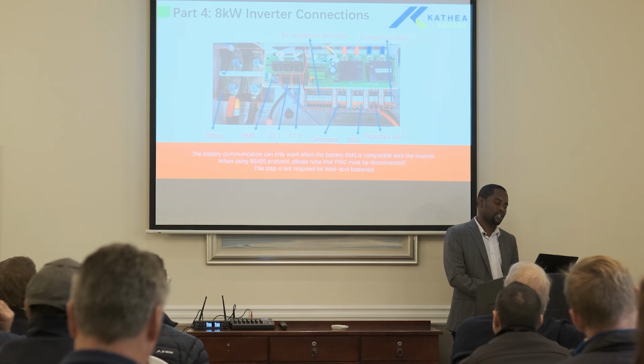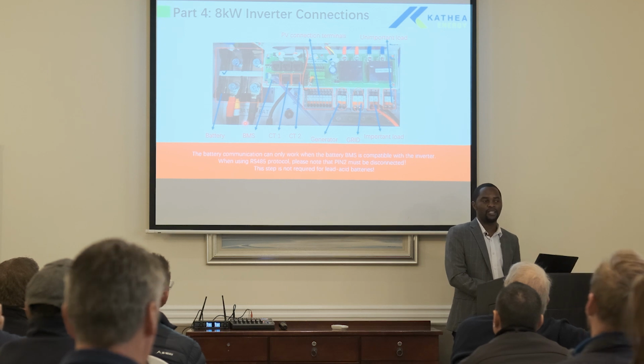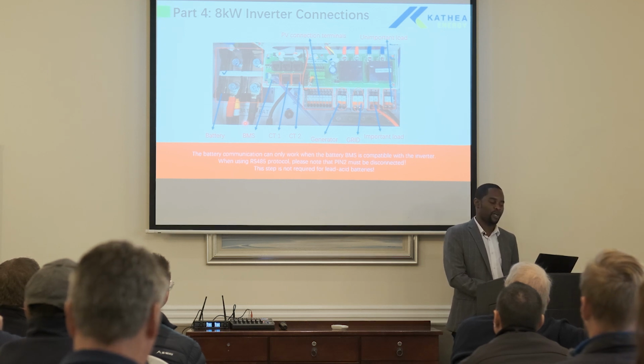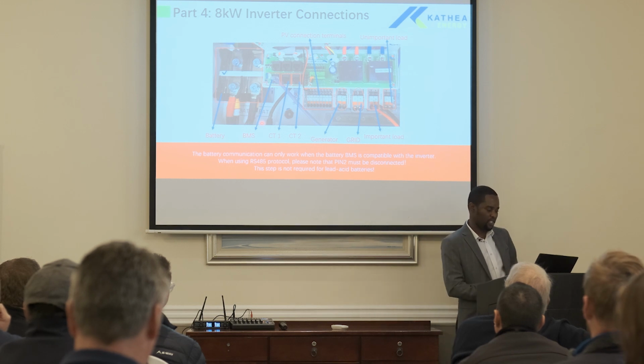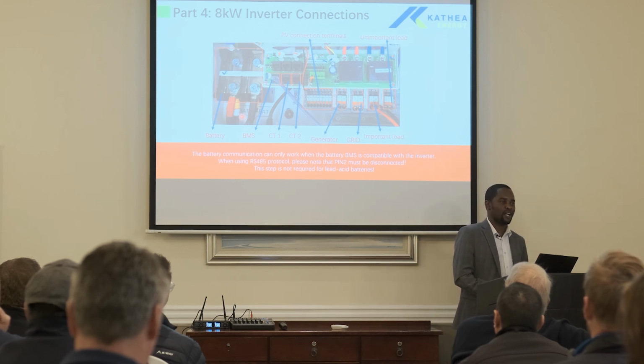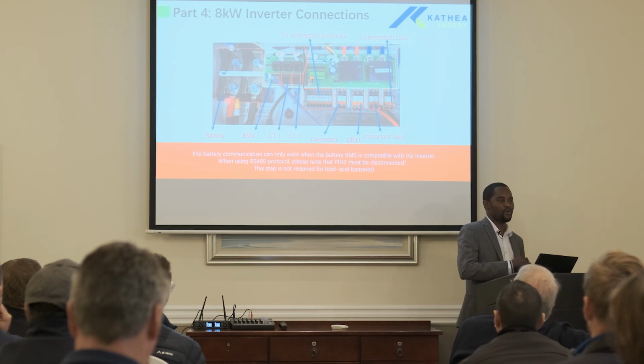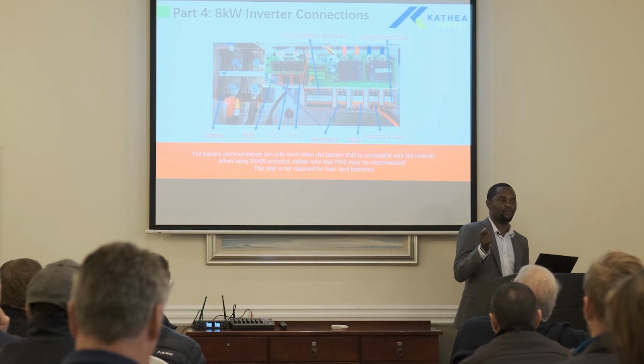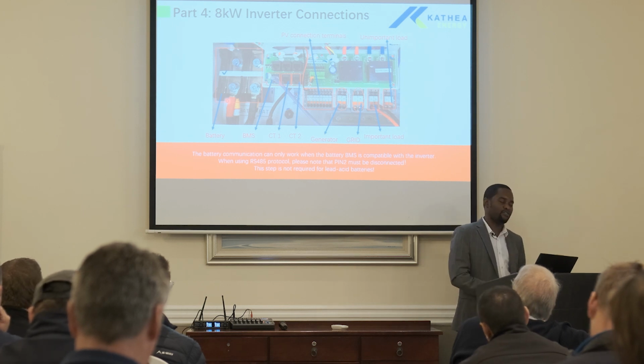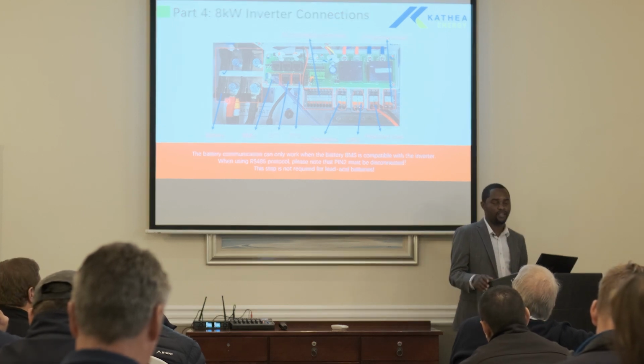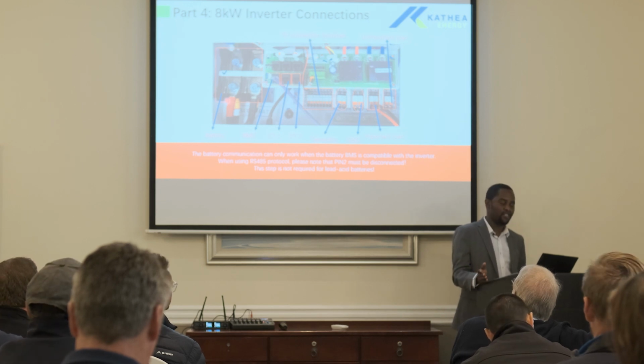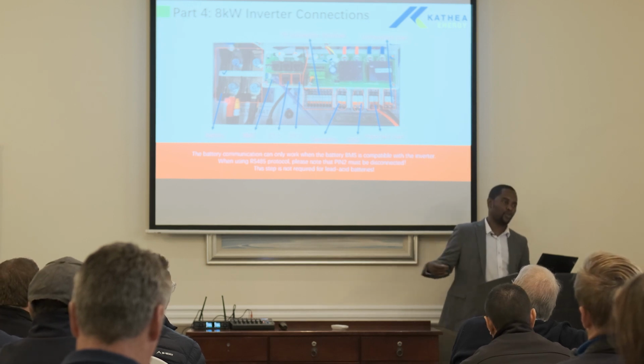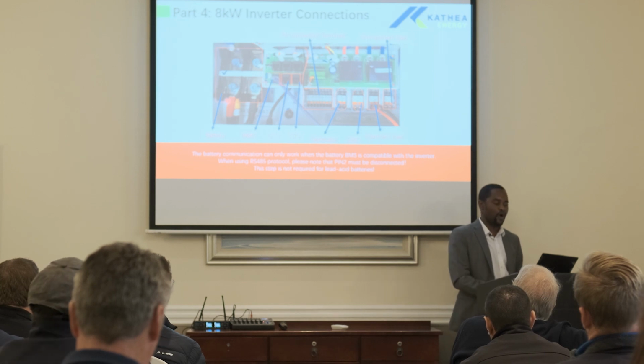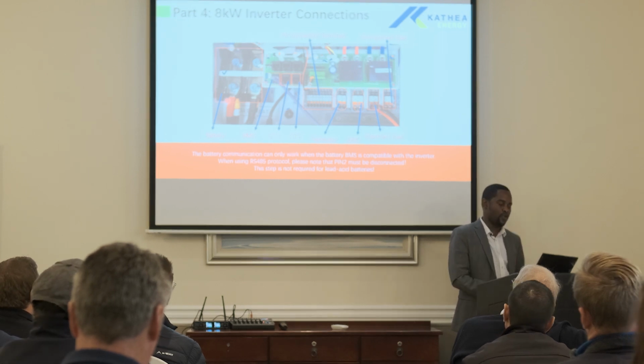Now, you see, even here, they use the same color of cable. Normally, others use red and black, but you can have someone just buying one red, then he puts these shrouds, and at the end, he puts the color codes now. So if you make a mistake when you are coding those colors, you may think that you've got a negative while it's a positive, because you just put a red color. So if you can, try to separate and have different colors, but if you can't, then ring it out with your meter. Make sure you ring it out before you wire it or before you switch on your inverter.